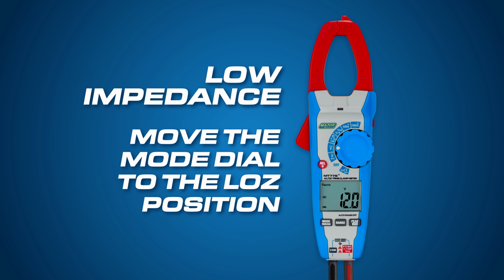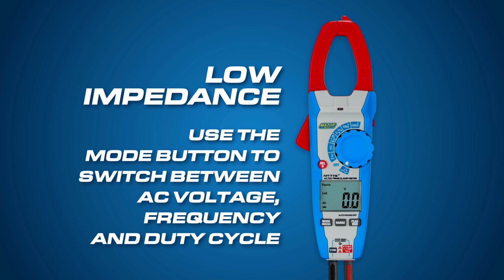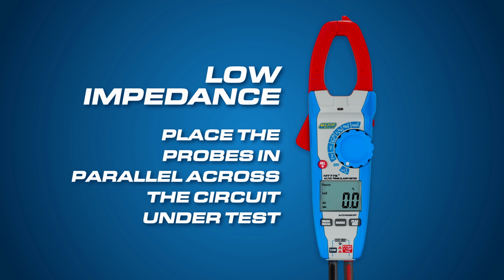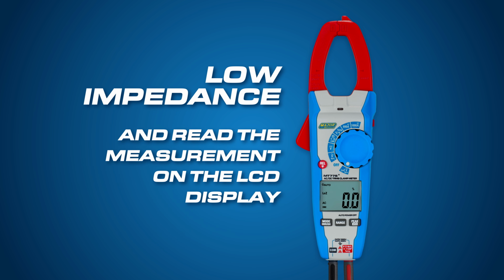For low impedance testing, move the mode dial to the LOZ position and use the mode button to switch between AC voltage, frequency, and duty cycle. Place the probes in parallel across the circuit under test and read the measurement on the LCD display.